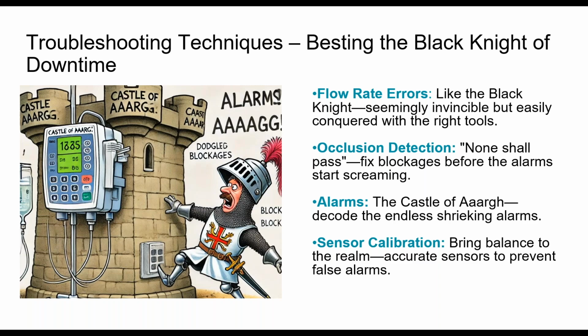And sensor calibration. When we're doing PMs, if it's PM worthy - and that's up for debate sometimes about different technologies - but let's assume your infusion pumps are worthy of some sort of preventative or planned maintenance. Make sure your sensors are tested, your flow rates are tested, your occlusions are tested, and your alarms. Make sure your sensors actually work.